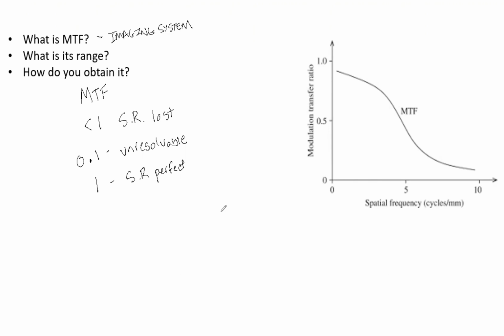It doesn't mean the spatial resolution is perfect, but that the reproduction of it is perfect. So as I was saying, there is no good or bad. All you care about is the baseline. An imaging system can degrade due to failure of components or old age. And what you care about is what the imaging system started at, and over time, is it getting worse? So ideally, you don't want a really steep curve.